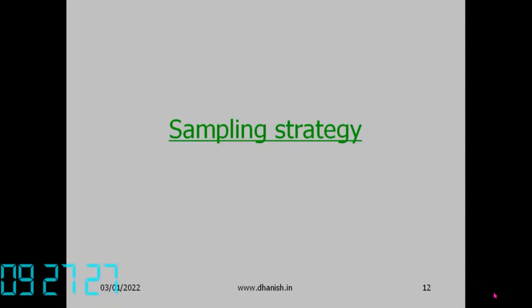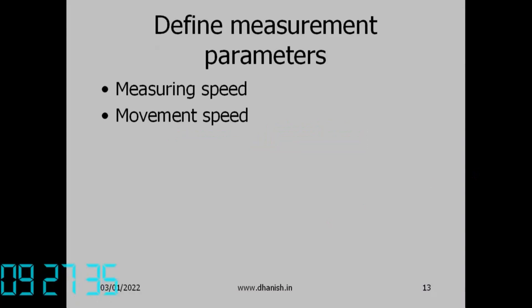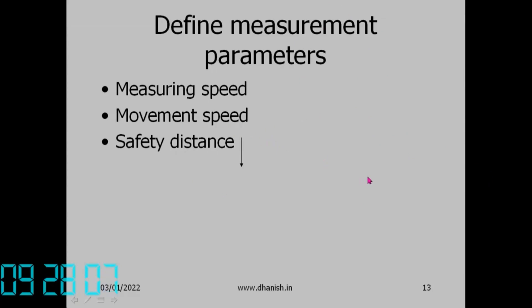Measurement parameters: measuring speed is the slow speed at which the probe contacts the workpiece; movement speed is the fast speed for traveling between points, similar to rapid travel in CNC machines; safety distance is the distance from the surface at which the machine switches from movement speed to measuring speed.